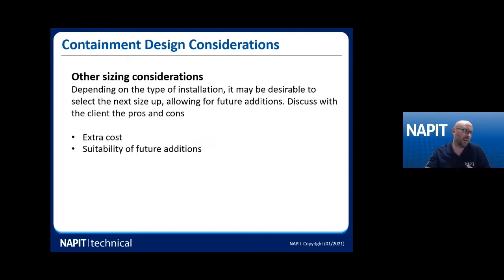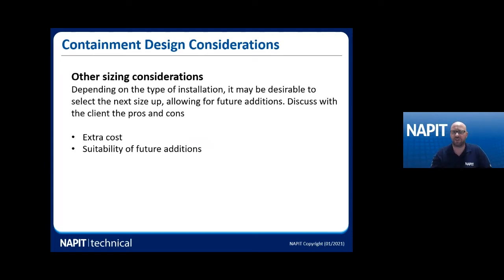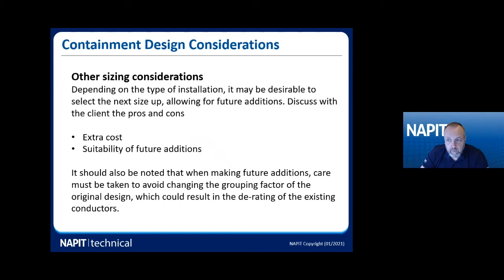We also need to consider other things in our design. Depending on the type of installation, it may be desirable to select the next size up to allow for future additions, and you really need to discuss the pros and cons with the client. For example, the client might say they're building a workshop now with a certain number of machines, but they're expecting to expand later in the year. You need to have that conversation — if most of the current equipment is single phase but next year they plan to add three-phase induction motors, the smaller trunking and tray you've put in might not be adequate.